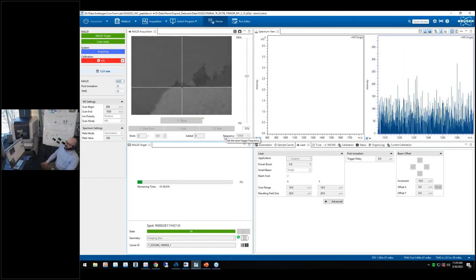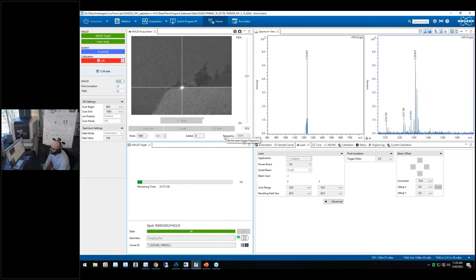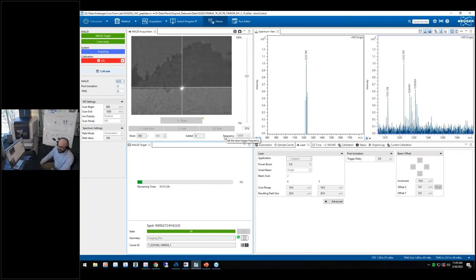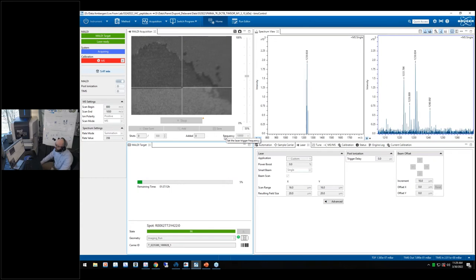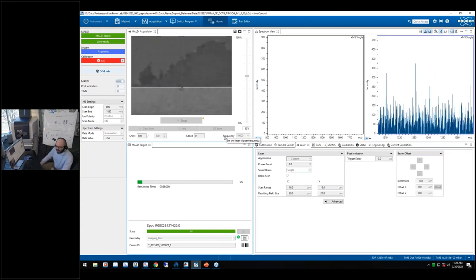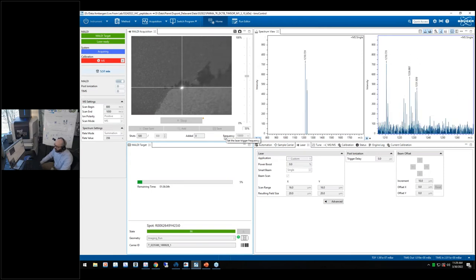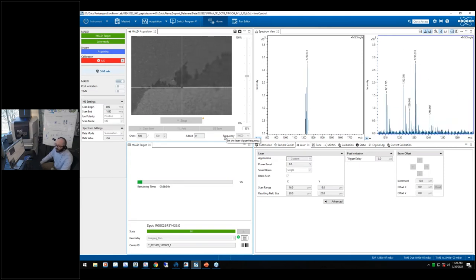So other features about the instrument, you mentioned resolution specifically. The resolution is a mass dependent thing. As you get to higher masses, you start losing resolution. That's a natural phenomenon of time of flight instruments. But around 1,000, we usually see around 40,000 to 60,000 to be on the safe side.